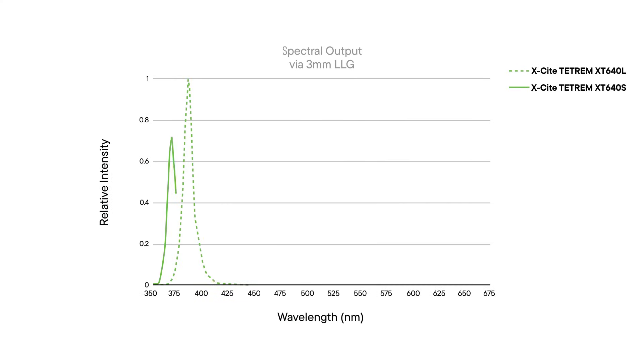With TETREM, you can excite the most common fluorophores such as DAPI, FITC, mCherry, and Cy5. Like other EXCITE products, TETREM has two UV LED options available in a 365nm as well as a 385nm version for DAPI excitation. Users can choose the version that best fits their filter sets.